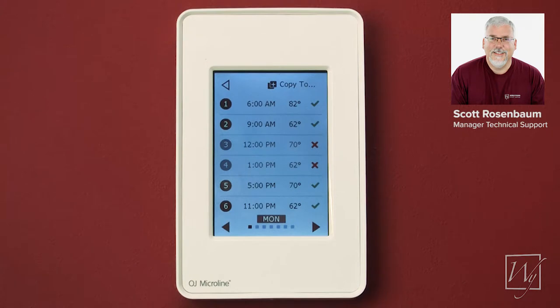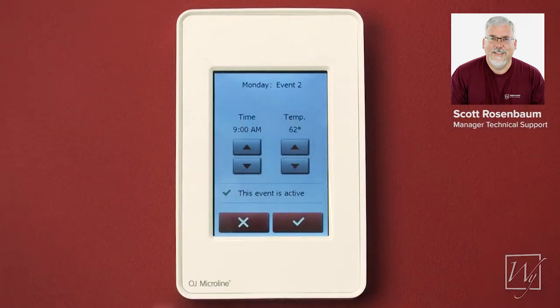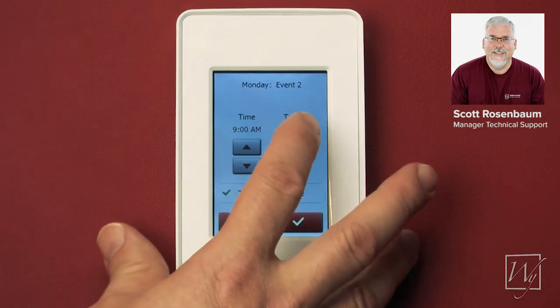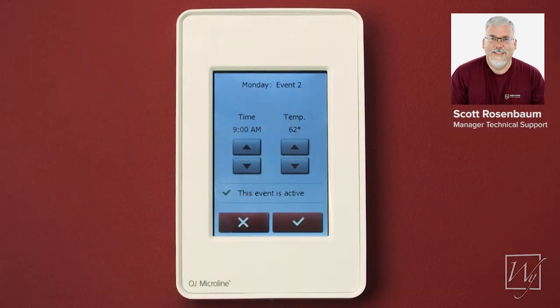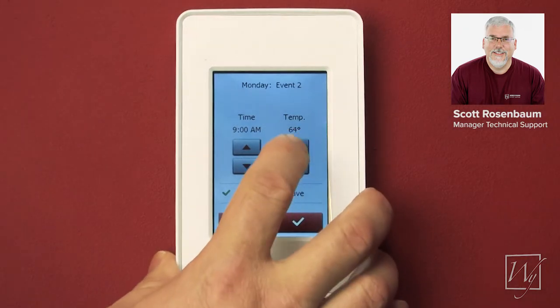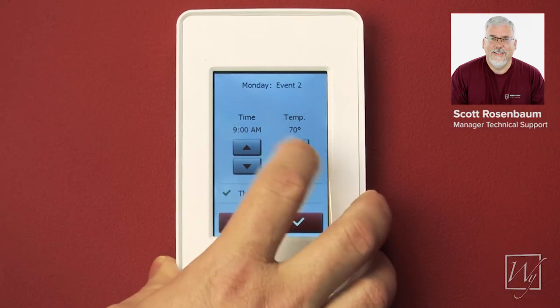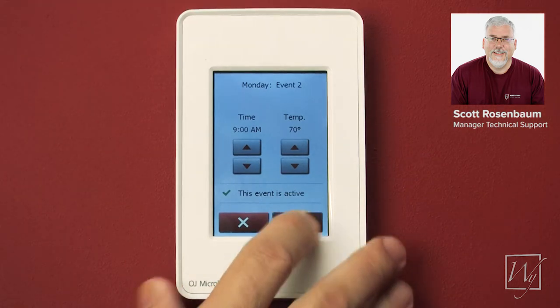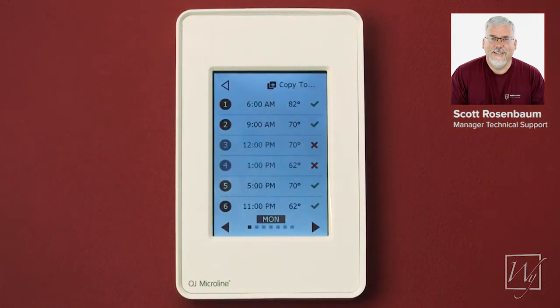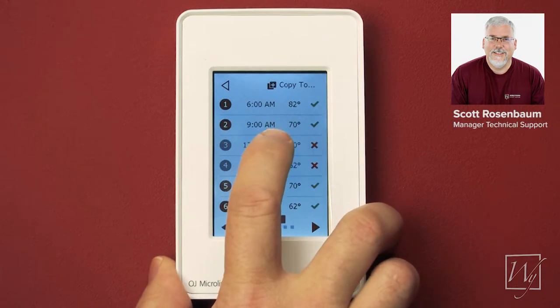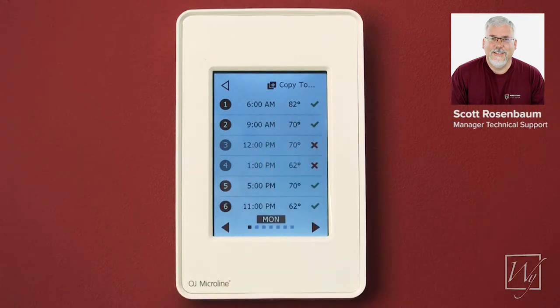Then at 9 a.m. I want it to go down to something that's not quite so cold, because the colder you make this reading, the longer it will take for the next session to heat up. So I'm going to set this to a little bit higher temperature, something like 70, and press OK. So at 6 a.m. it's going to go up to 82, and at 9 a.m. it's going to drop to 70.